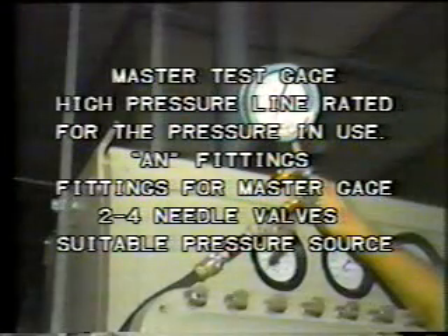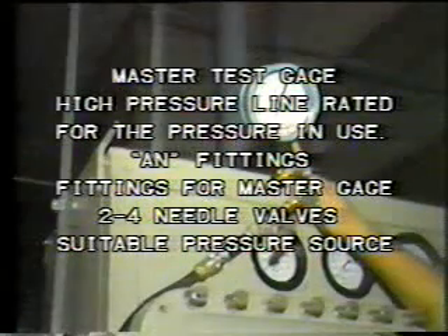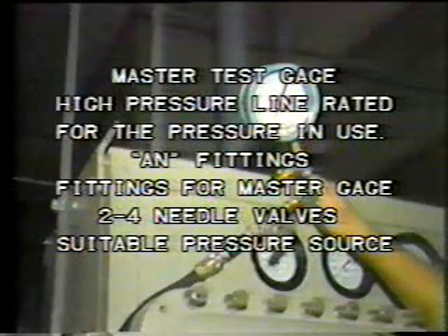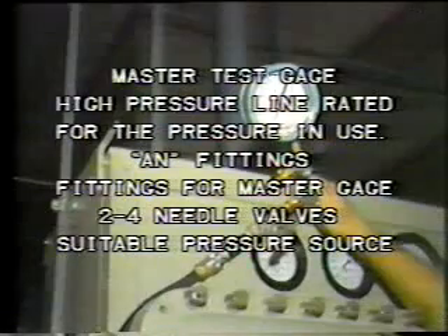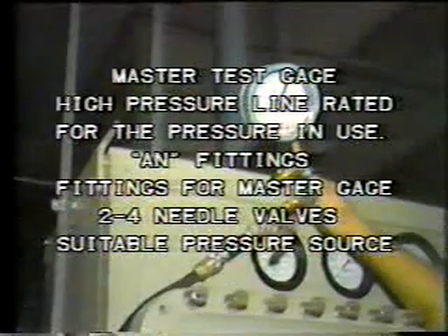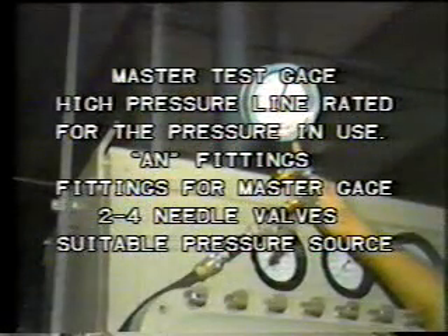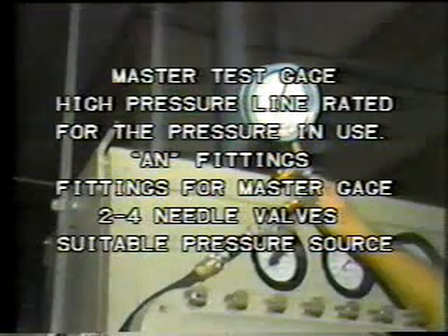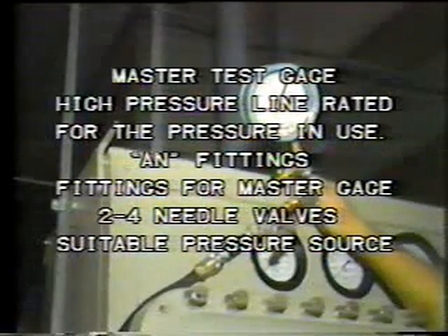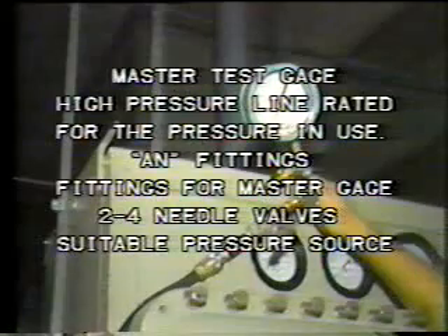To perform the calibration, you will need a master test gauge, several high-pressure flexible lines with the correct AN fittings, proper fittings for master gauge connections, 2 to 4 needle valves rated for the pressure in use, and an acceptable pressure source.